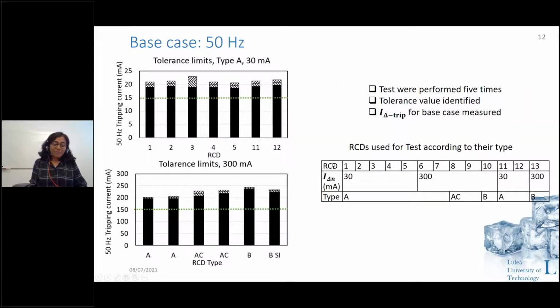Okay, so according to the standard 61008, every test has to be performed 5 times, and an average value of the result has to be considered. So keeping that in mind, we first built a base case with only 50 Hertz component, and we had a total of 13 RCDs of different types, like type A, AC, and type B, and different ratings, 30 milliampere and 300 milliampere. I will be presenting results for 30 milliampere and 300 milliampere RCDs separately. And the base case, what you see, is the average value after 5 tests.